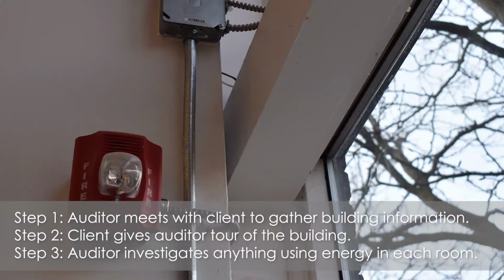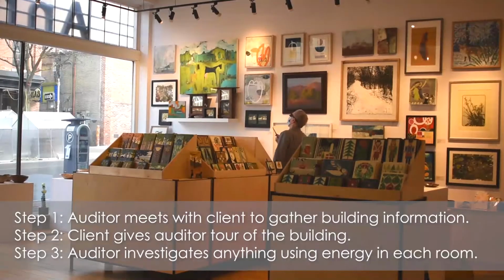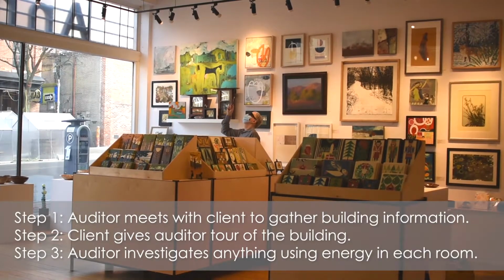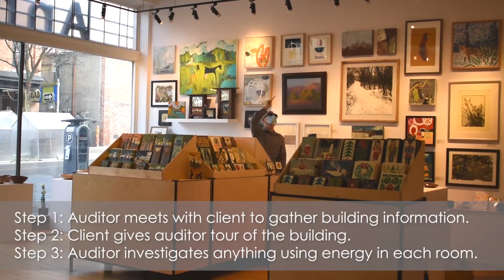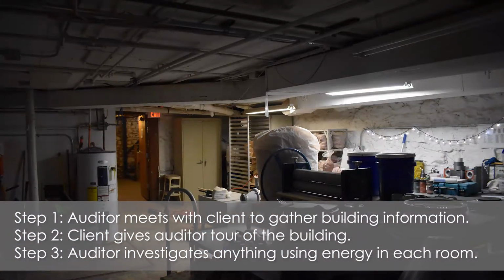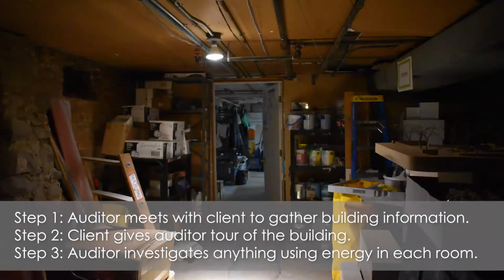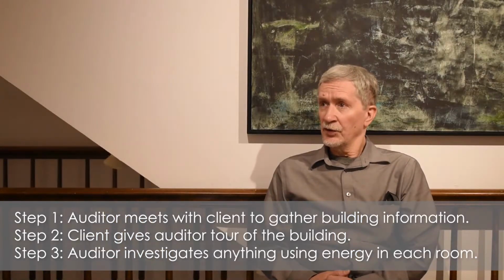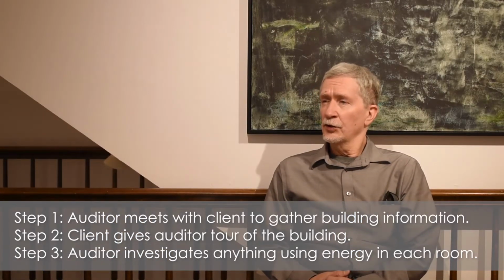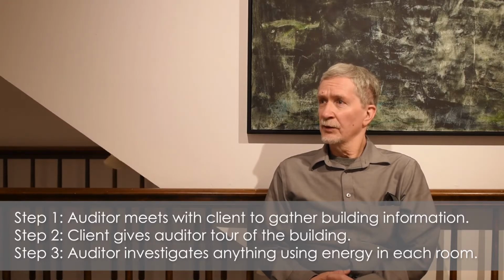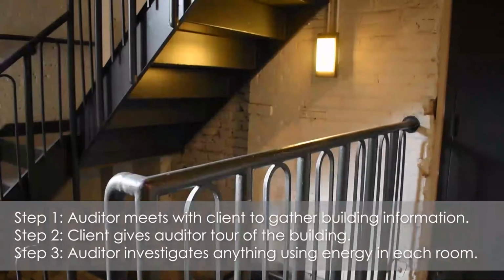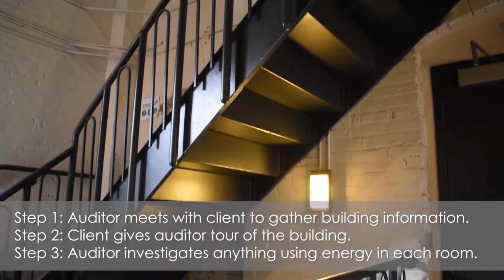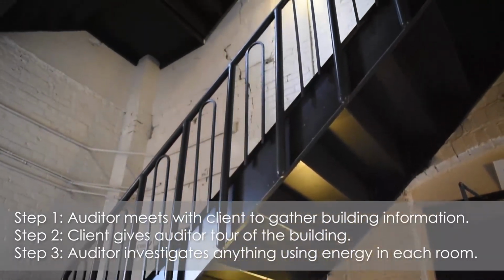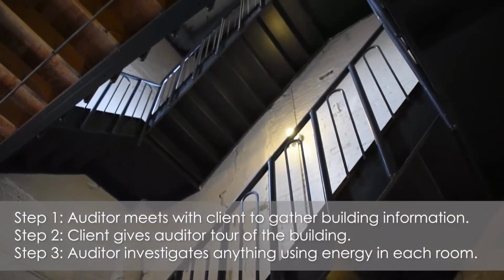If there's equipment on the roof, we go on the roof to document all the equipment that's up there. If there's a basement with equipment in it, we go down in the basement and take a look at all that equipment. We check out the doors and windows to see what shape they're in. We try to determine what levels of insulation are in the building. So if there's an attic, we will go up into the attic. We probe the walls to see if there's any insulation in the walls.